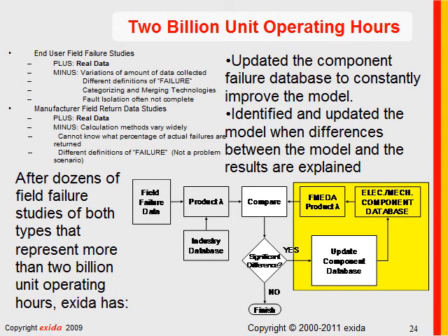After dozens of field failure studies of both types, this summer we completed a major field failure study on pressure transmitters with remote seals, such that the total number of unit operational hours has reached over 2 billion.